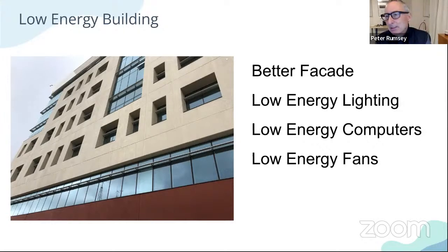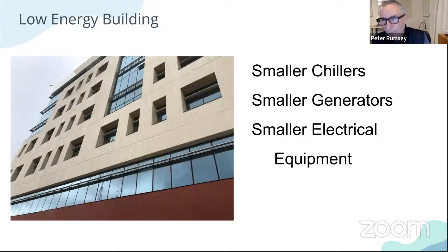So you put all these things together, and this particular building is in Bangalore, but they have buildings in many different parts of India. Remember the thumb rule: even in India, it's around 400 square feet per ton, 500 for office buildings. Emphasis is now on building buildings where the design is 800 or 900 square feet per ton, and there's no problem. So they have half as much cooling as the market standard building, and they're operating perfectly. Wonderful, wonderful way.